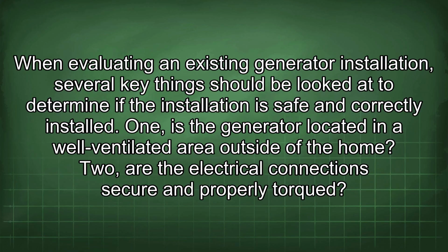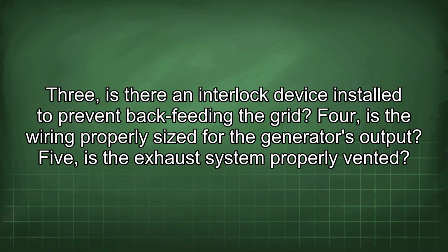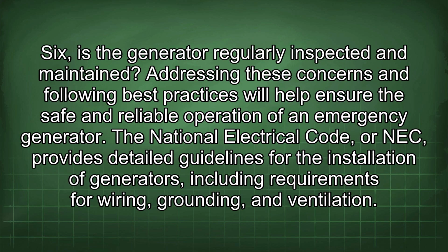When evaluating an existing generator installation, several key things should be looked at to determine if the installation is safe and correctly installed. 1. Is the generator located in a well-ventilated area outside of the home? 2. Are the electrical connections secure and properly torqued? 3. Is there an interlock device installed to prevent backfeeding the grid? 4. Is the wiring properly sized for the generator's output? 5. Is the exhaust system properly vented? 6. Is the generator regularly inspected and maintained? Addressing these concerns and following best practices will help ensure the safe and reliable operation of an emergency generator.